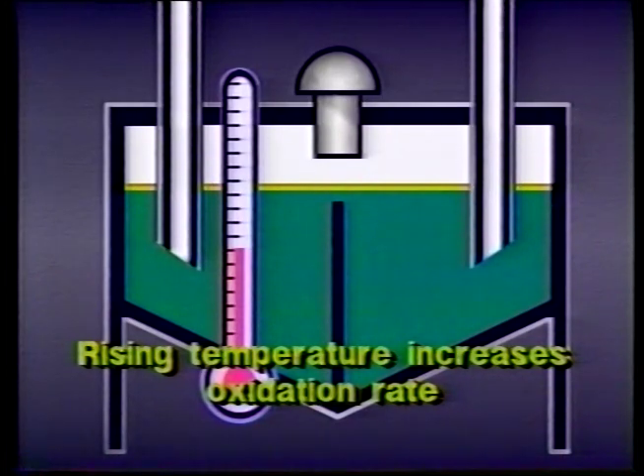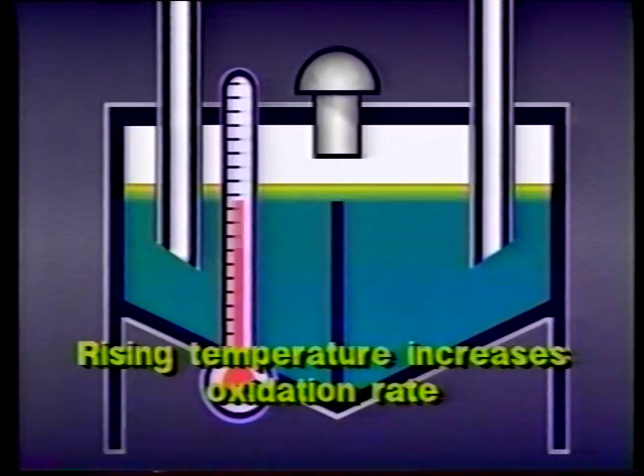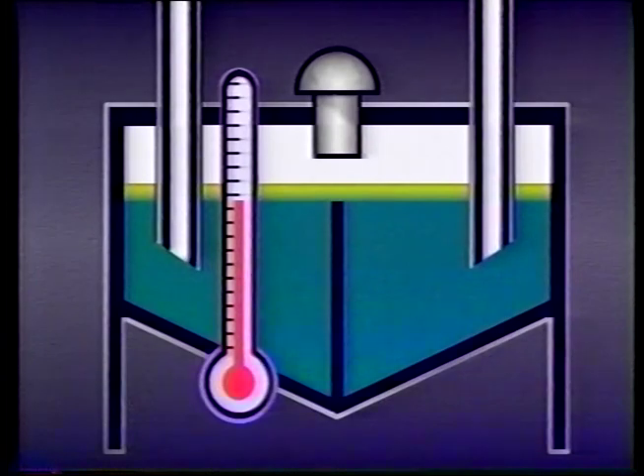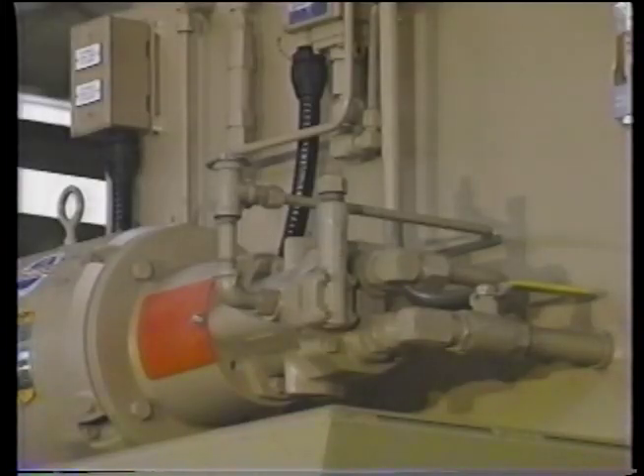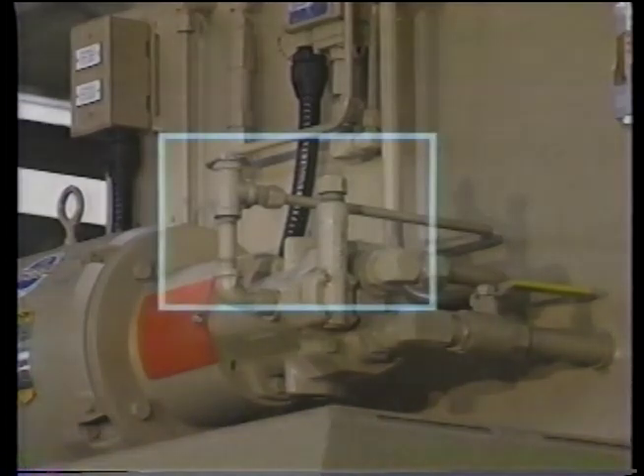Generally, oil oxidizes twice as fast as normal for every 20 degree Fahrenheit rise above an average reservoir temperature of 130 degrees Fahrenheit. Oxidation inhibitors can be added to the oil to slow the oxidation process in the reservoir. However, oxidation inhibitors have little effect when oxidation occurs at the outlet side of a hydraulic pump.